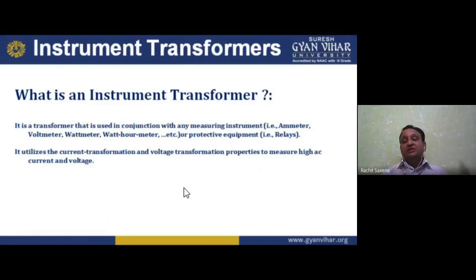So if I want to measure in kilo, that is 10 raised to the power 3, 1000 volt, 1000 watt, 1000 ampere, then a simple voltmeter, wattmeter, ammeter is not sufficient. So I need a different instrument known as instrument transformer, and this is used in conjunction with measuring instruments, ammeter, voltmeter, wattmeter, watt hour meter, etc., or protective equipment, relay. Relay is just like a switch, which is used for protection purposes.